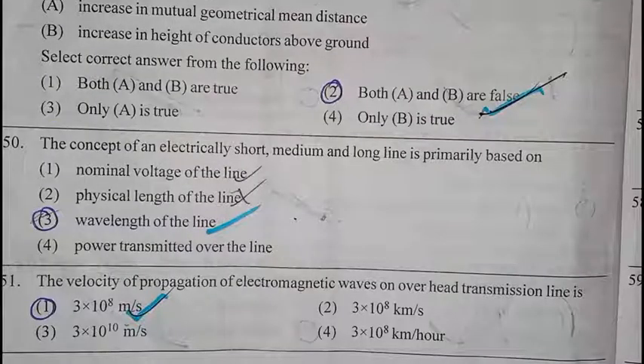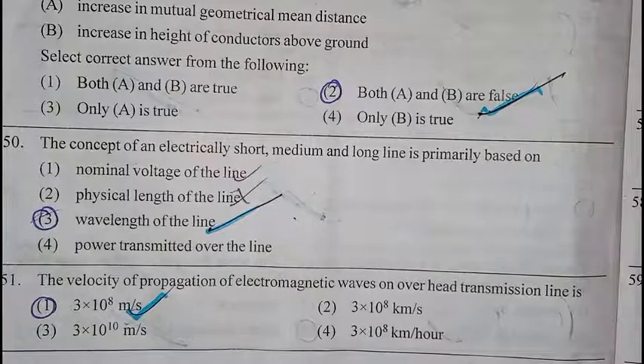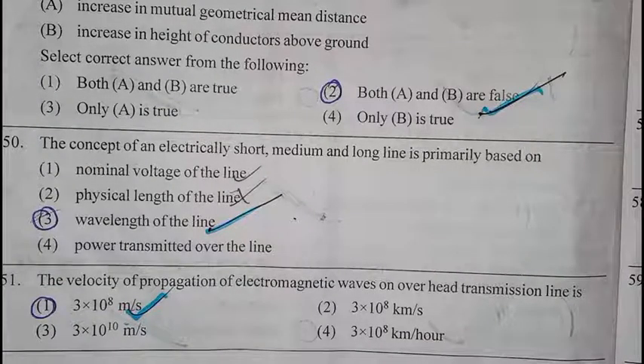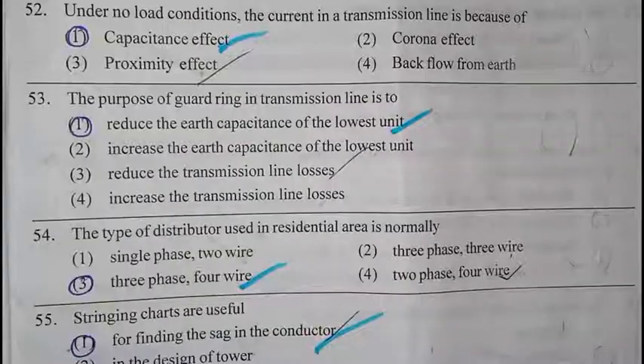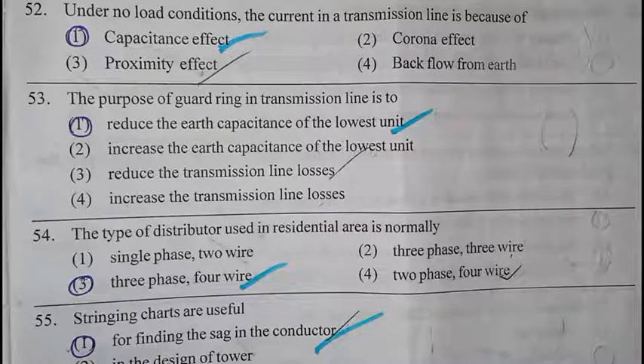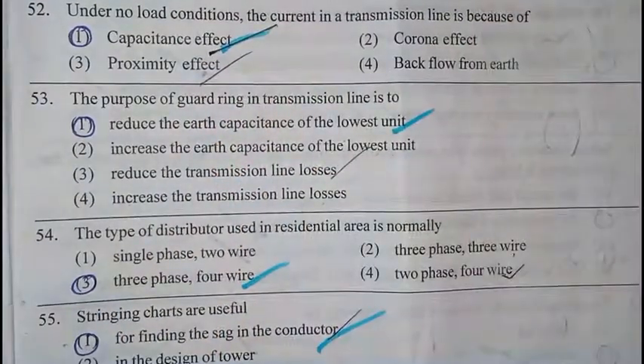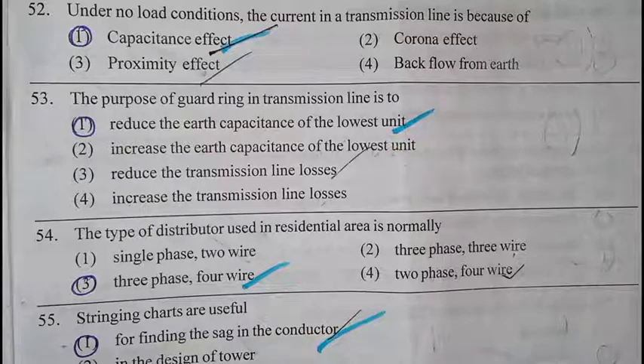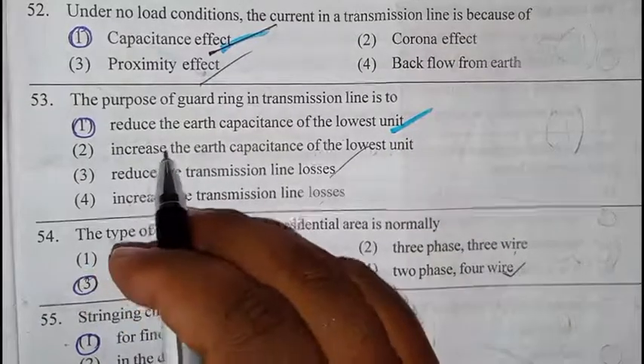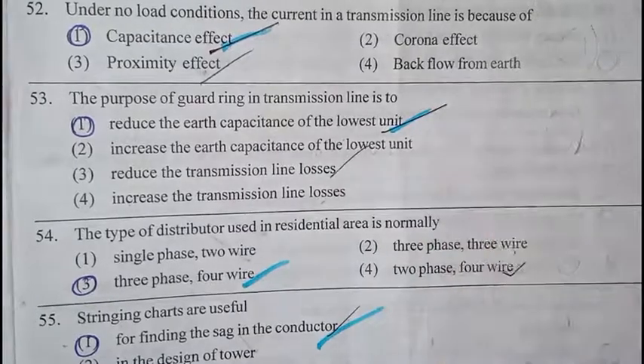Next, question number 50. The concept of an electrically short, medium and long line is primarily based on. Answer: wavelength of the line. Question number 51. The velocity of propagation of electromagnetic waves on overhead transmission line is. Answer: 3 into 10 power 8 meter per second. Question number 52. Under no load condition, the rise in voltage at the receiving end of the transmission line is because of. Answer: capacitance effect. The purpose of guard ring in transmission line is to. Answer: reduce the earth capacitance of the lowest unit.